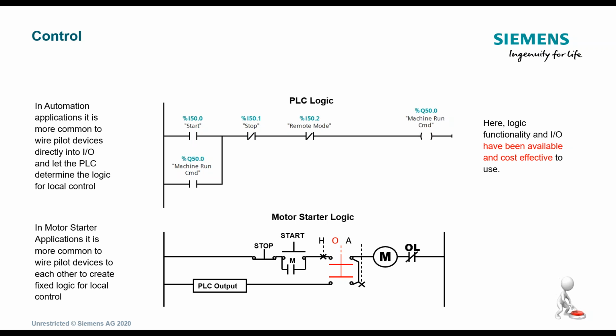Logic is a cost-effective way of using it. Logic helps you. It's not hardwired. Back in the day, in the early part of my career, I was in control relay, and some of you who've been around this world of controls definitely remember the relay panels, the clicking and clacking of just relay logic going on inside that panel. The I/O is hardwired. It's hard to change that. It's hard to maneuver if you wanted to do some type of different logic. But with the controllers introduced and ladder logic and other types of programming schemes, it is easier to work on that.